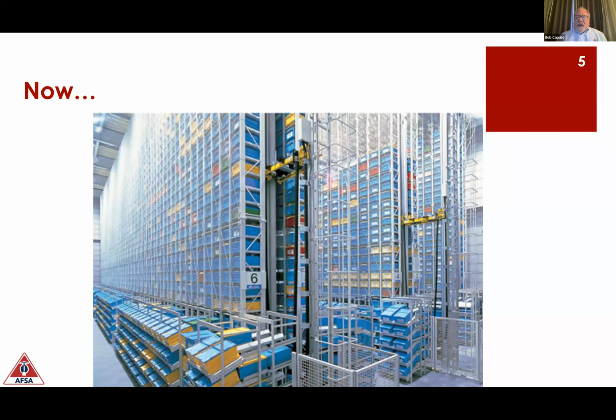So that's one impact, the height of the storage, because fire moves both vertically and horizontally. And the rapidity at which that fire grows tends to have the strongest effect as the fire moves upward. So now I've got this raging fire in a very tall storage facility, and the heat release rate is so intense that in the early years of standard fire sprinklers, no matter how much water the sprinkler put out, the droplets wouldn't reach the base of the fire. They literally would evaporate before they got to the bottom. So this higher challenge drove the need for better technology.